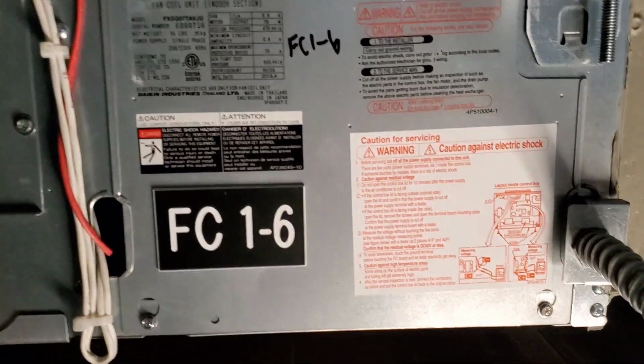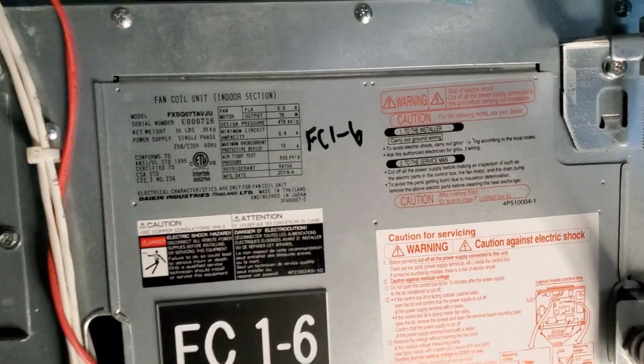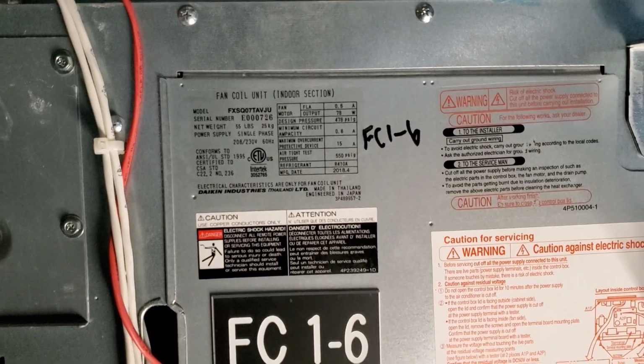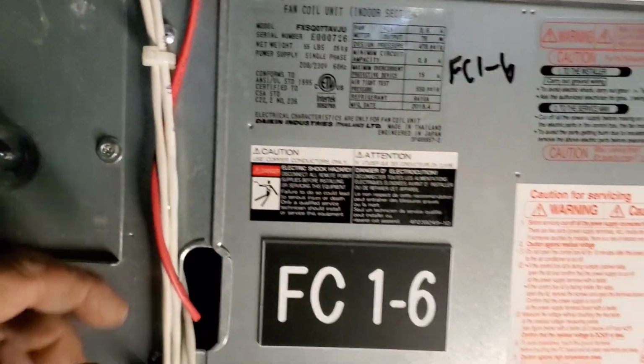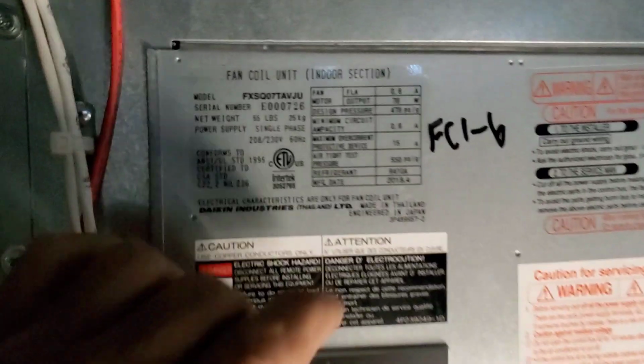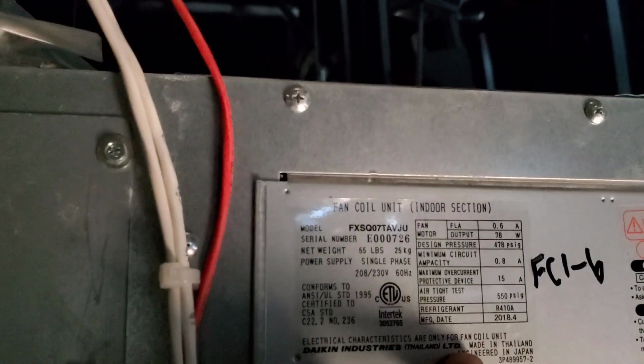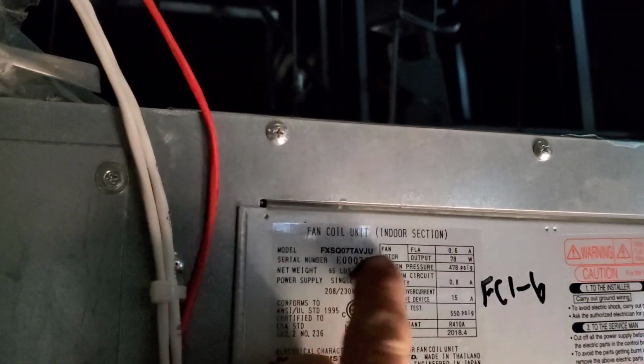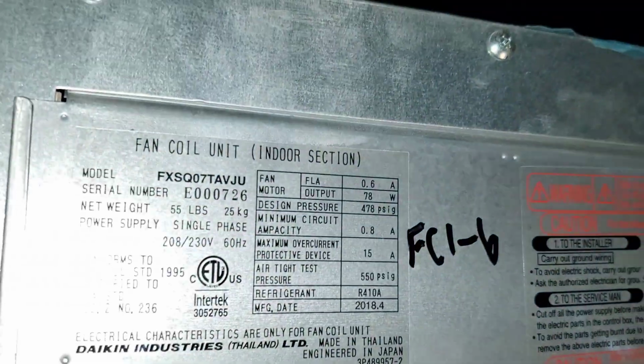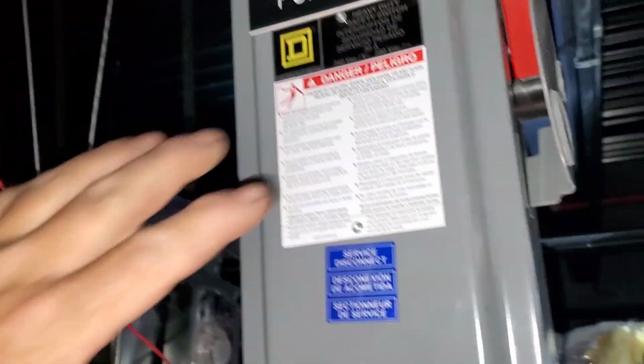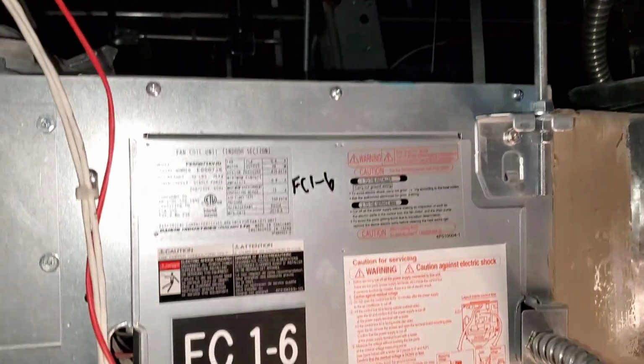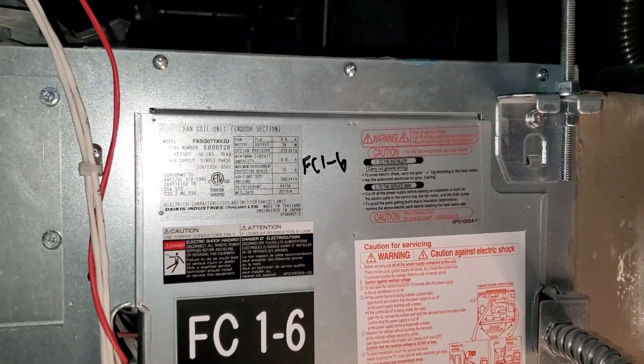All right, working on these Daikin units. Brand that's been cursed since they bought out Goodman. Little tiny air handler. 15 amp fuses blown again. The fan full load amps is only 0.6 amps on these things. 0.6 amps, 78 watts.